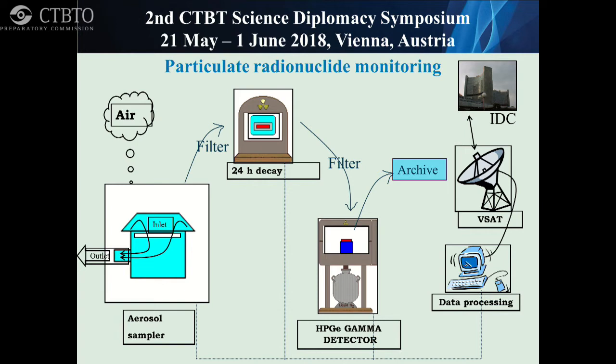This filter is then moved into a decay chamber, because a lot of the particulates coming into the filter are background, radon daughters, which are always in the air and, depending on the station location, can be much more or less. They are likely short-lived, and the 24 hours is a compromise to let this big background, which constitutes a big noise for our detector, decay out as much as possible, but not to lose the relevant nuclides.